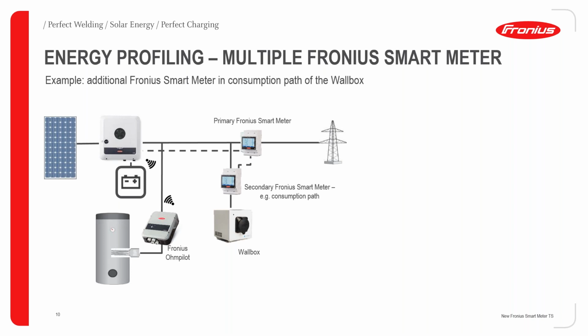Maybe you want to measure the whole consumption of the home, or in case you have a battery or a Fronius Ohmpilot, you need a smart meter, because this smart meter tells whenever there is energy going out from the home or coming from the grid. It has to tell whenever excess energy is going to the grid. This primary smart meter has to communicate to the inverter and tell the Ohmpilot, hey, now you can charge the heating device at home because I'm having excess energy. Or the other way around. If you have a battery, it's the same.